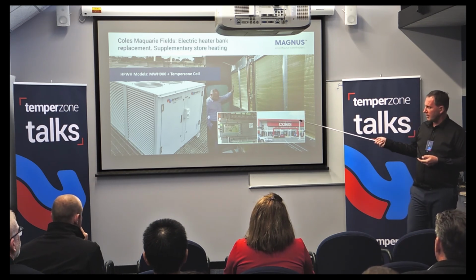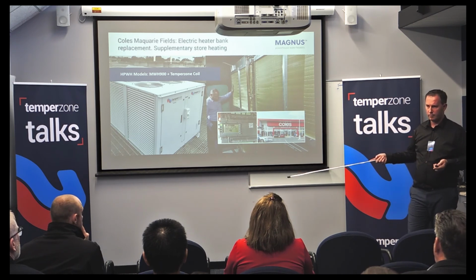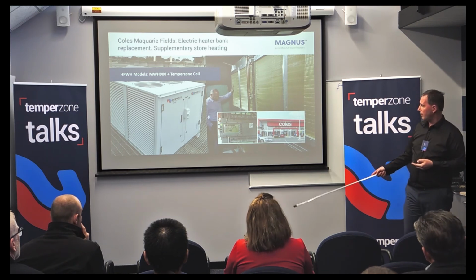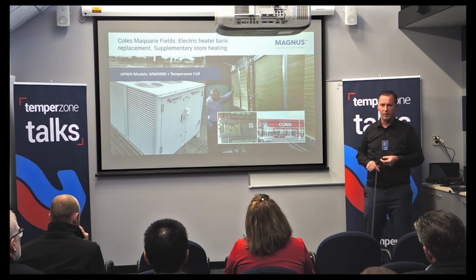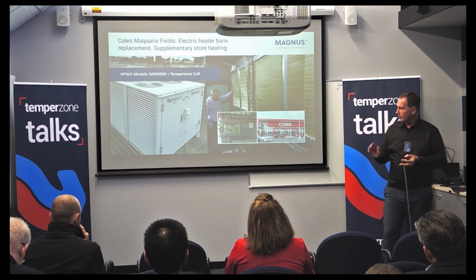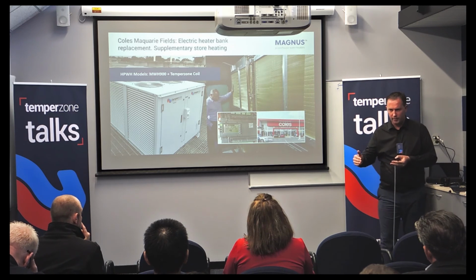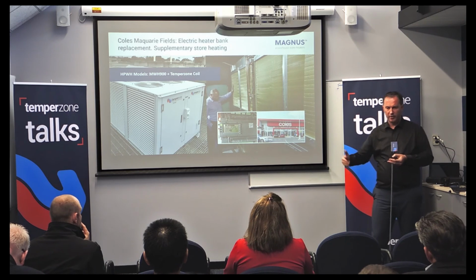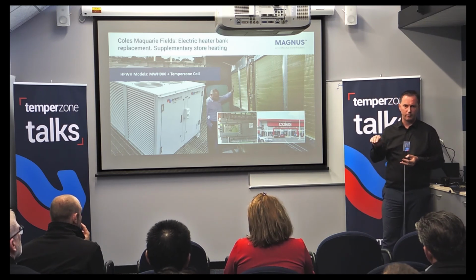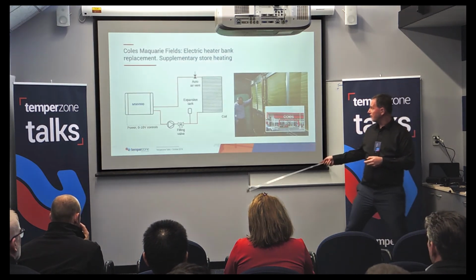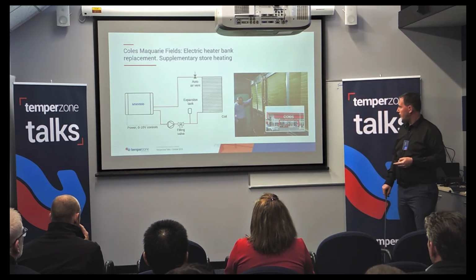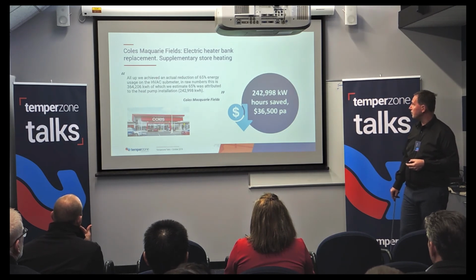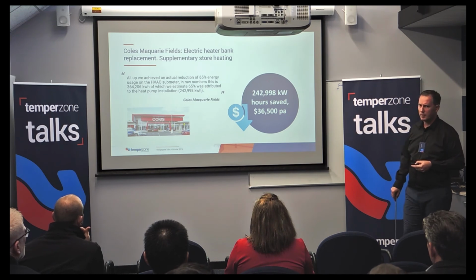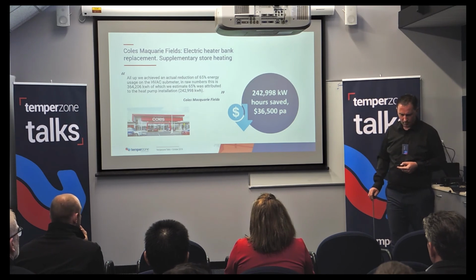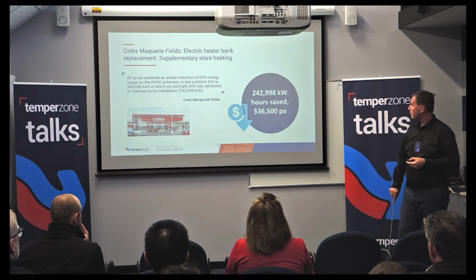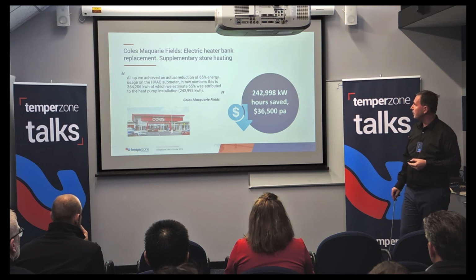So as the heating load increases, the pump goes faster to maintain the supply air. That increases water flow, which means more inverters turn on. Each inverter is run at the peak of its efficiency. As an inverter starts to go too quick, another one comes on, and another one, and it drops off the other one, so that the whole time each inverter is sitting at its peak efficiency. Here it is, a very basic, easy to apply system, which happens to save a lot of money in terms of energy over the year. This was done by Coles, their contractor, whose name escaped me, but they monitored the system over 12 months.